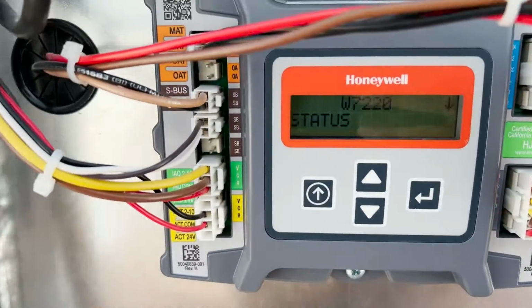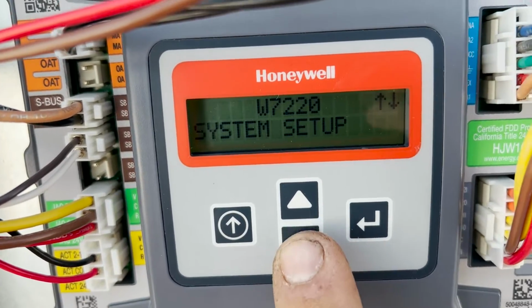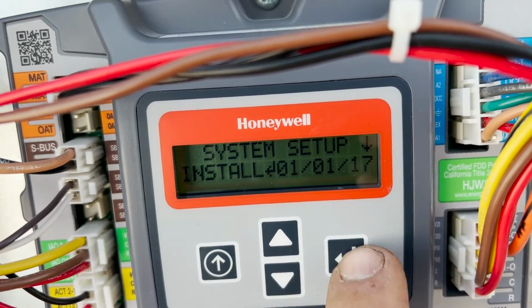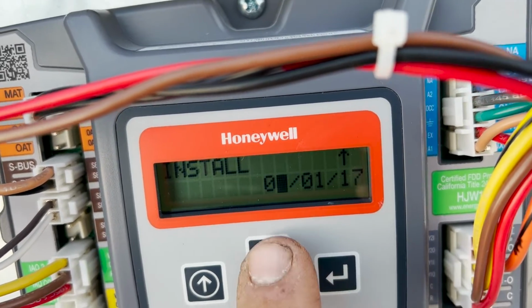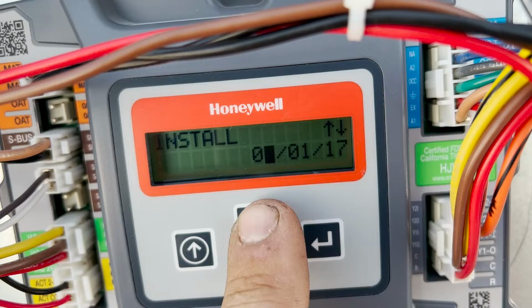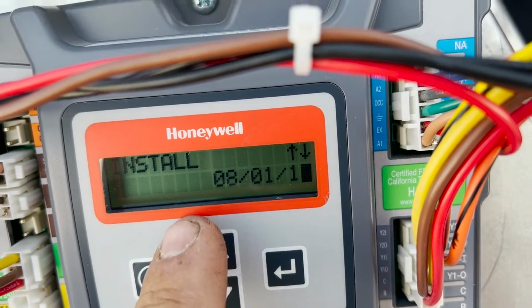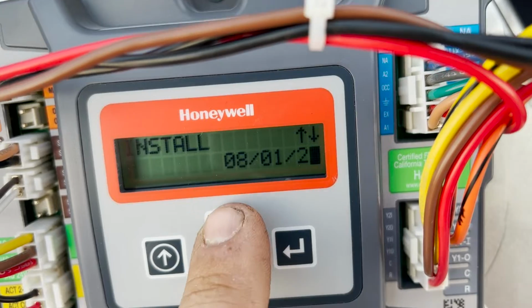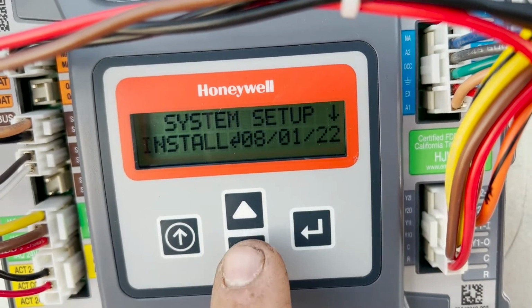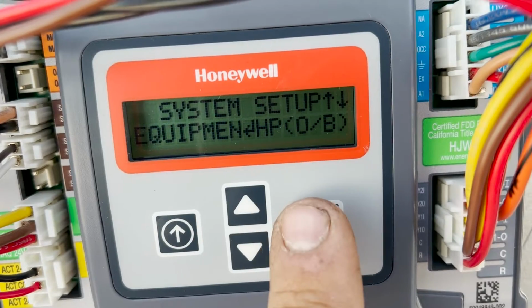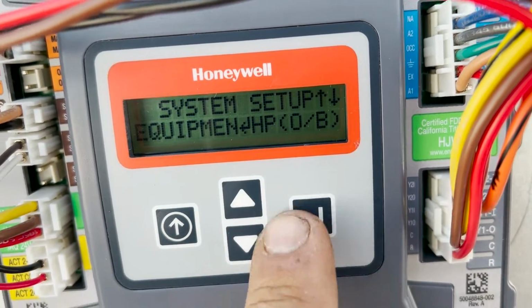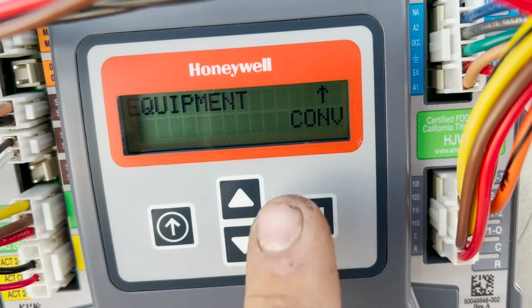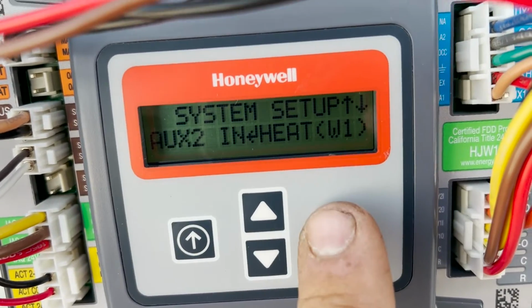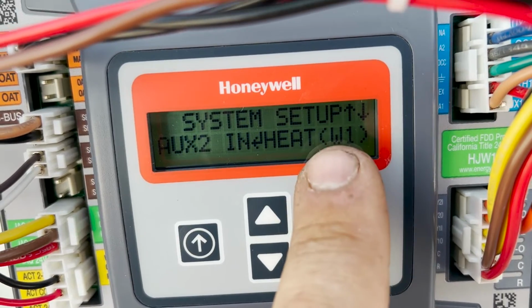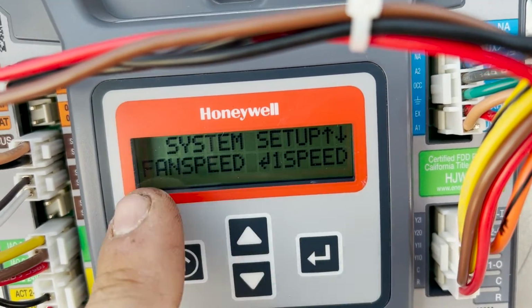All right, we're powered on. So we want to get to system setup. We're going to set our date. It is the 1st. Okay, changed. Fahrenheit, good. This is not a heat pump. This is a conventional system. Change stored. Yep, we have Y1 heat. Fan speed, this is a single speed fan.